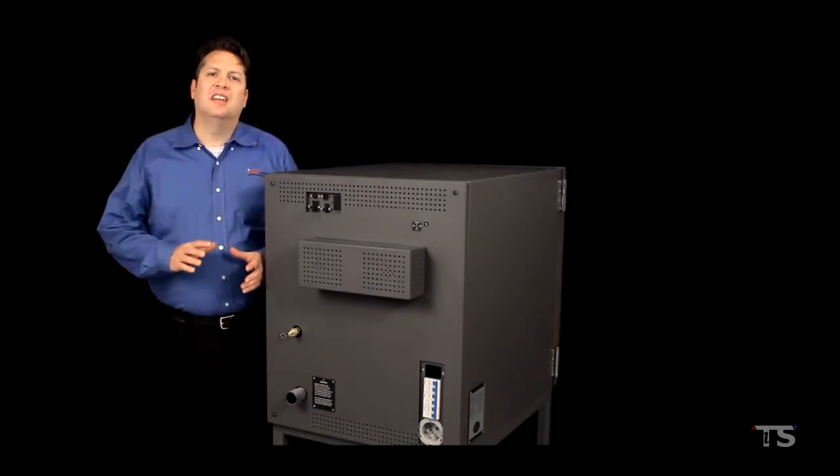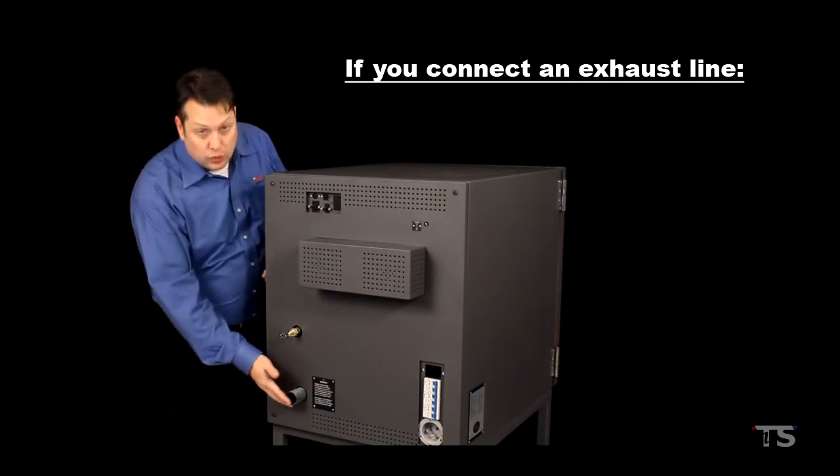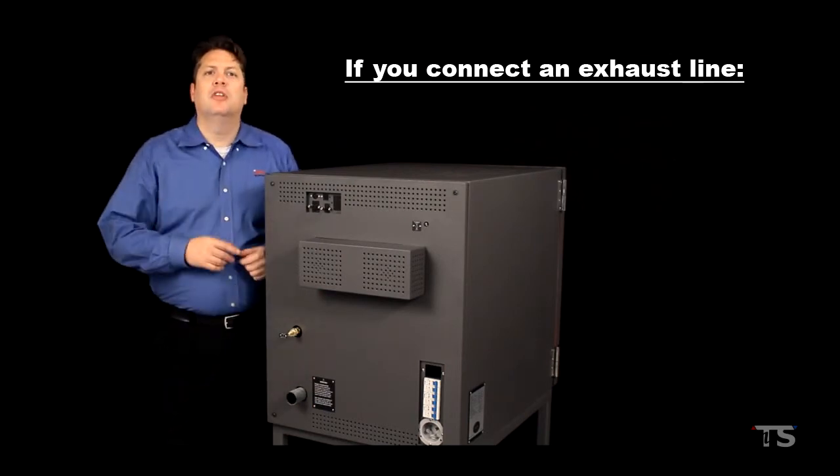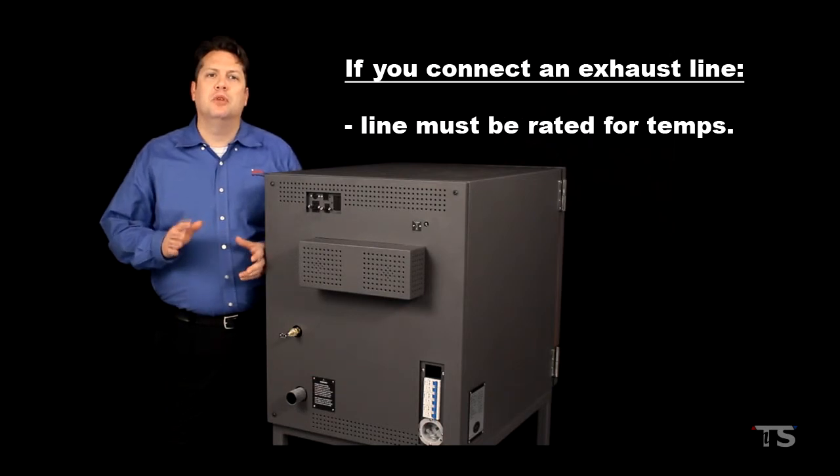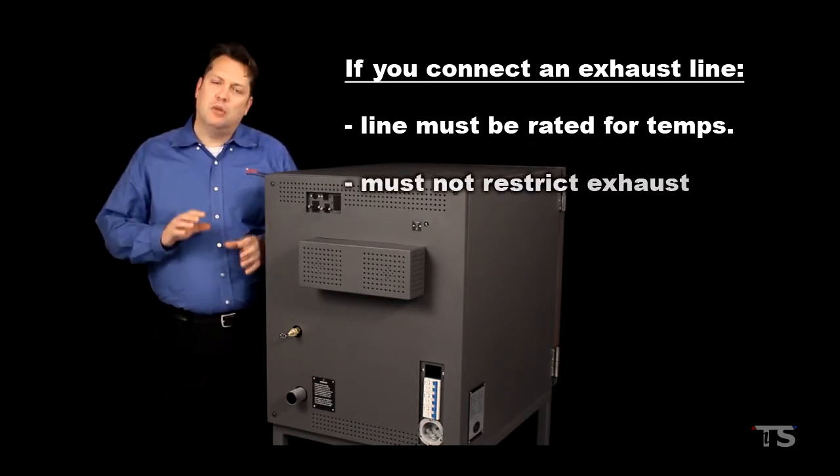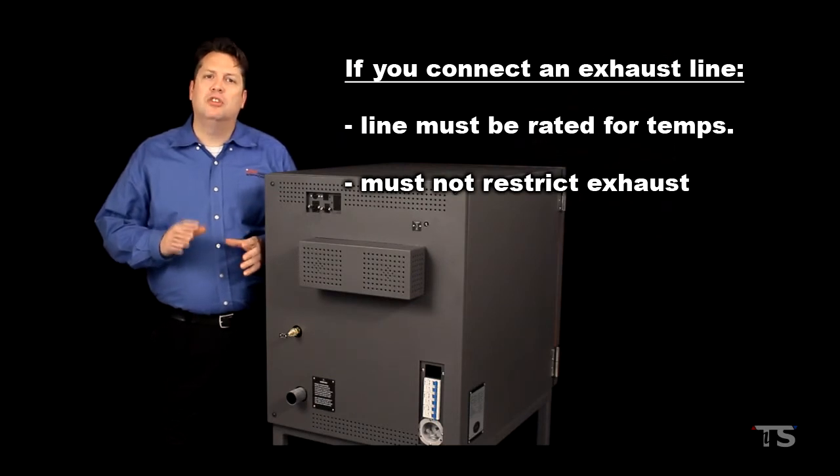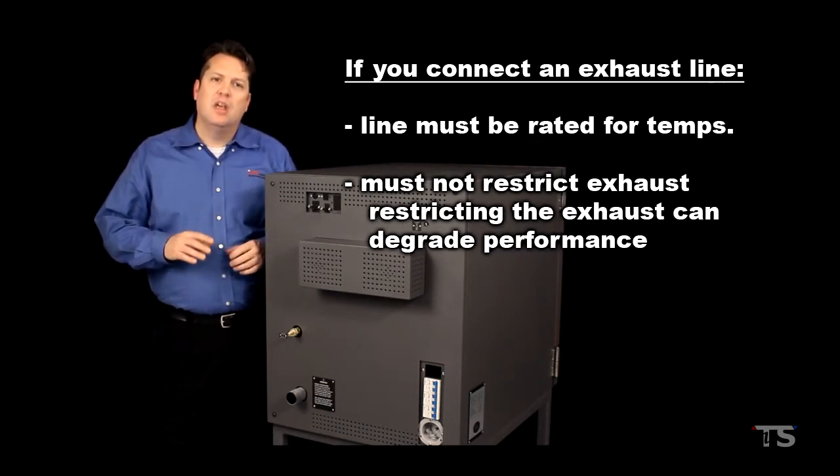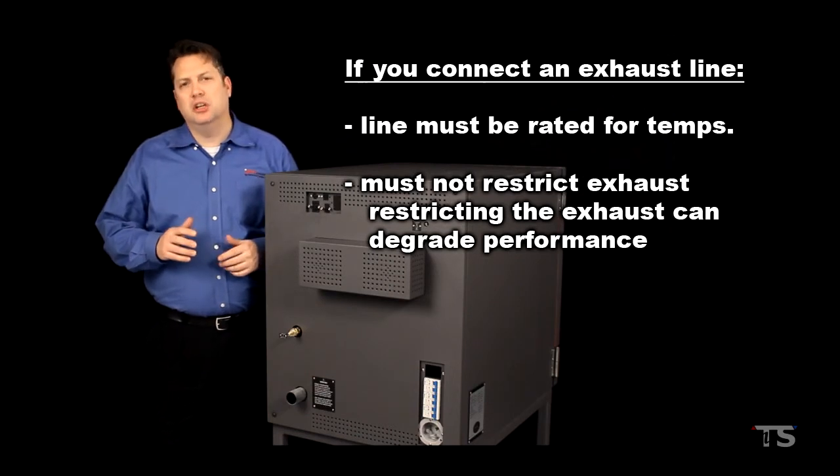If you need to connect any sort of exhaust line or facility exhaust system to the exhaust tube, make sure that the connections are rated for the temperature range of the equipment and make sure that these connections do not restrict the exhaust. Restricting the exhaust can lead to back pressure and a degradation of performance in your thermal chamber.